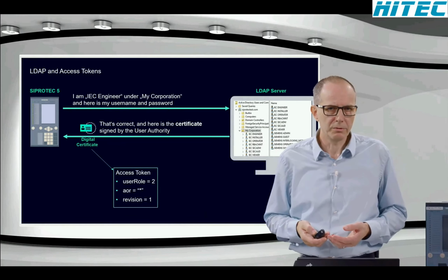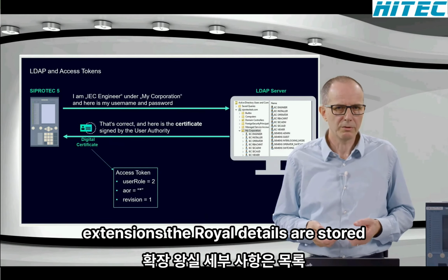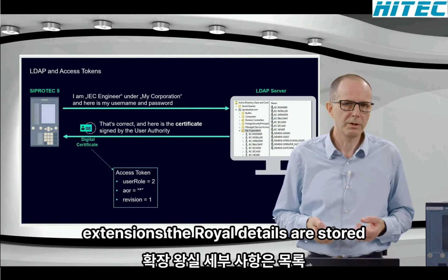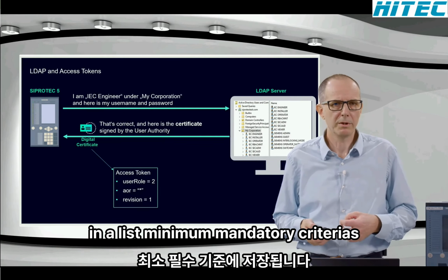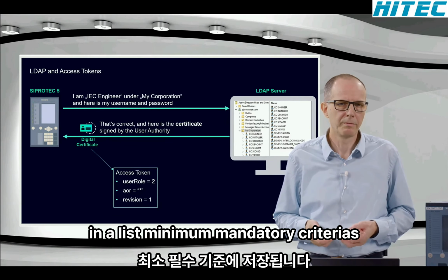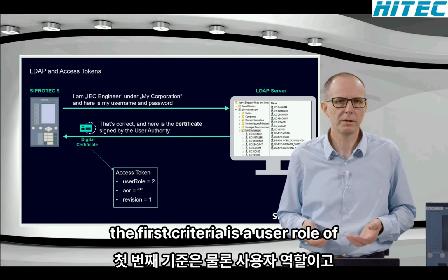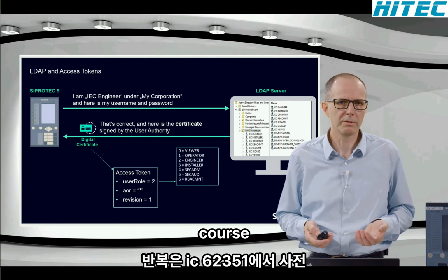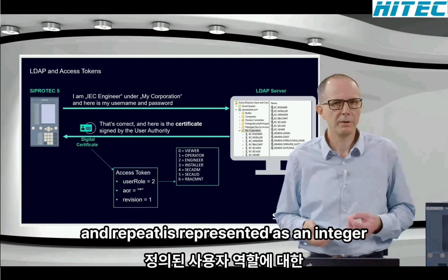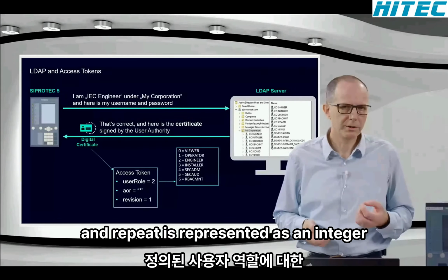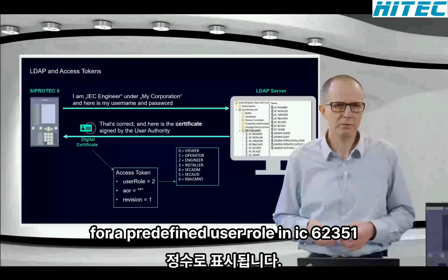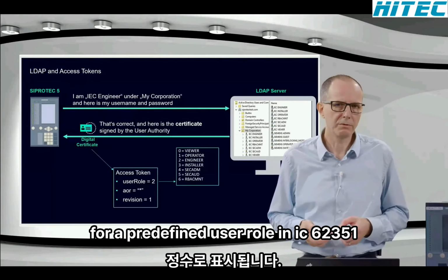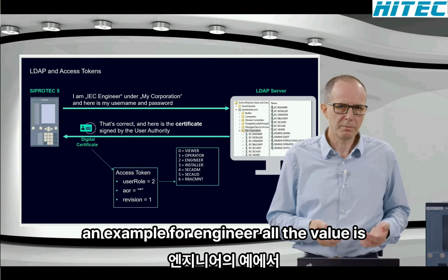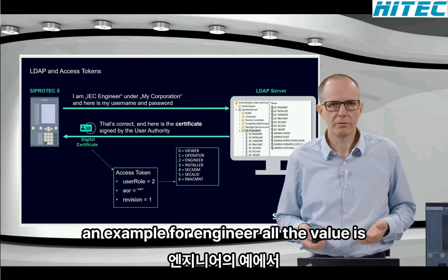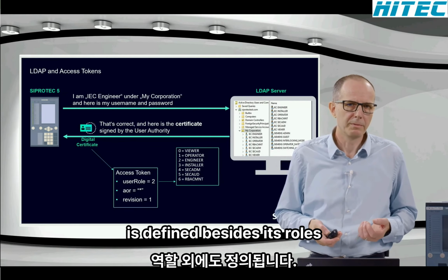According to IEC 62351 extensions, the role details are stored in a list with a minimum of three mandatory criteria. The first criteria is the user role, of course, represented as an integer for a predefined user role in IEC 62351. For example, for the engineer role, the value 2 is defined.